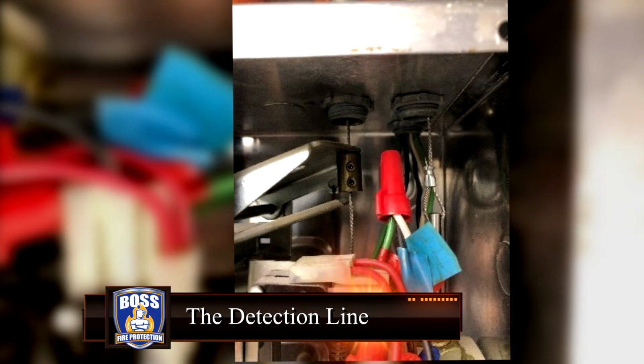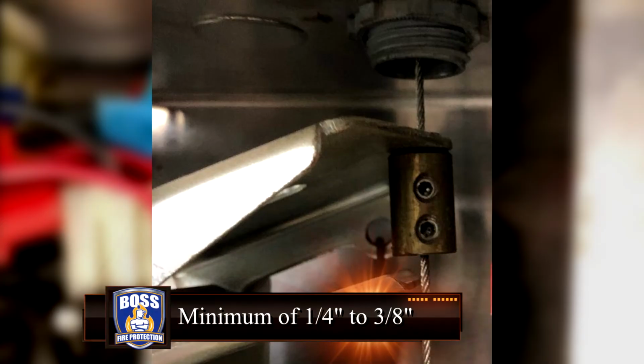The detection line. The detection line starts directly behind the micro switch and runs to the associated hoods connecting to each fusible link in the system. The detection line is set with a tension bar and spring for means of automatic activation for the wet chemical system. There should be a minimum 1/4 inch to maximum 3/8 inch clearance from the hammer to the hammer base. In the event of a fire, your fusible link will melt, triggering the hammer to drop, releasing the chemical agent to extinguish the fire.